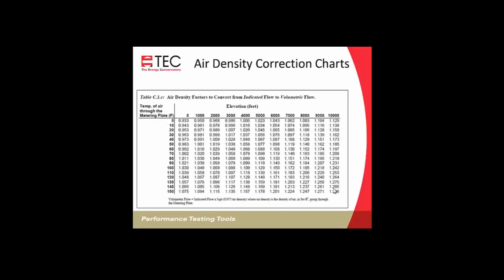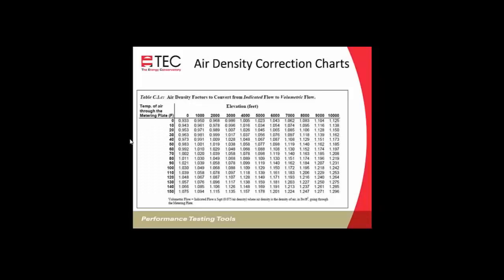Next, we'll talk about a density correction. There are charts that you can use to correct for density, both for temperature, for different temperatures of airflow moving through the plate, and also at different elevations. So for example, if you're measuring the flow with the air conditioning running, maybe you're at an extreme at 40 degrees, you'll see that at 40 degrees, you'll need to multiply it by 0.973 to get your actual airflow number there. So it's about a 3% difference, so not a huge difference, but it'll affect your flow readings.